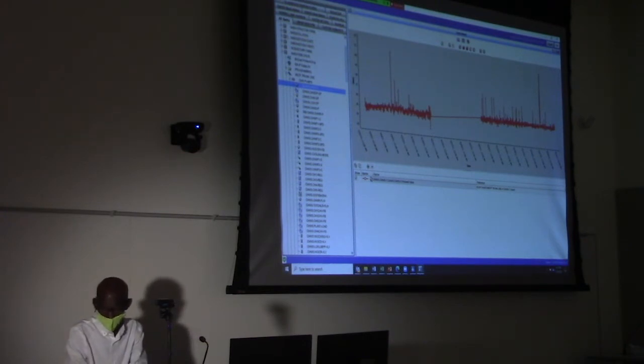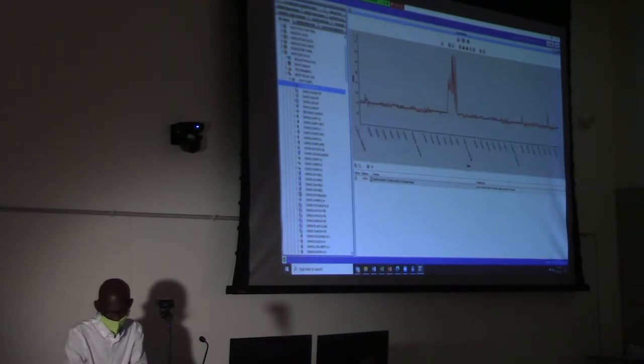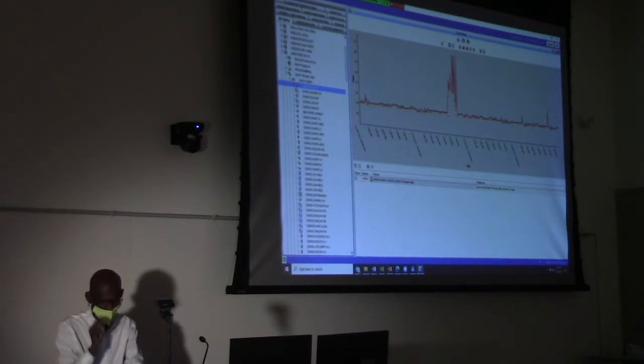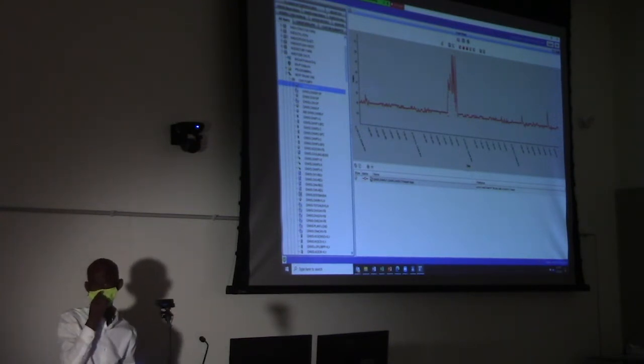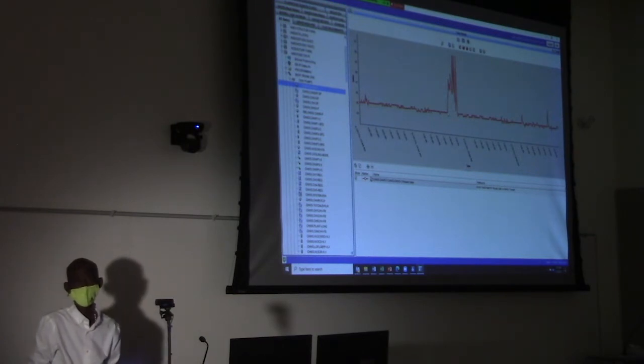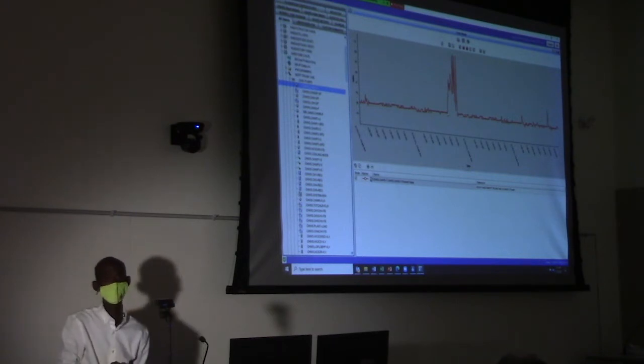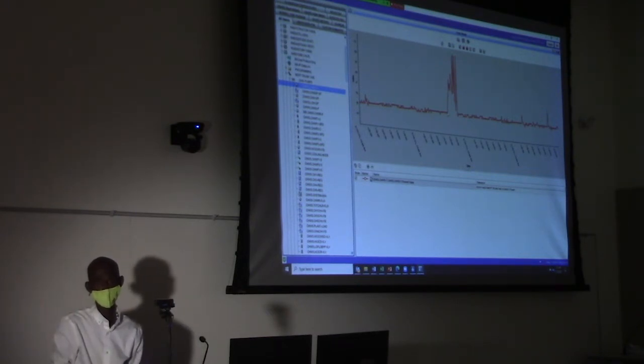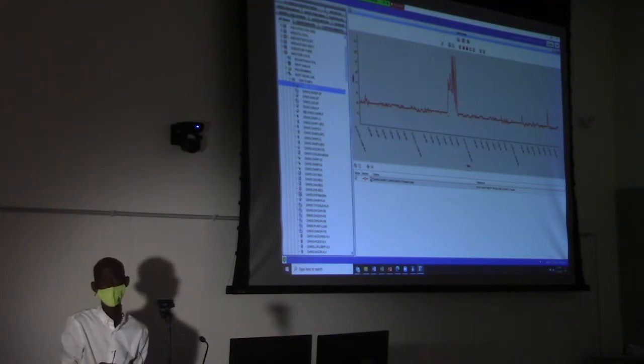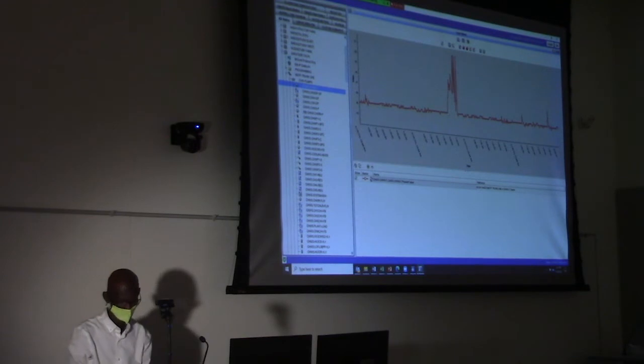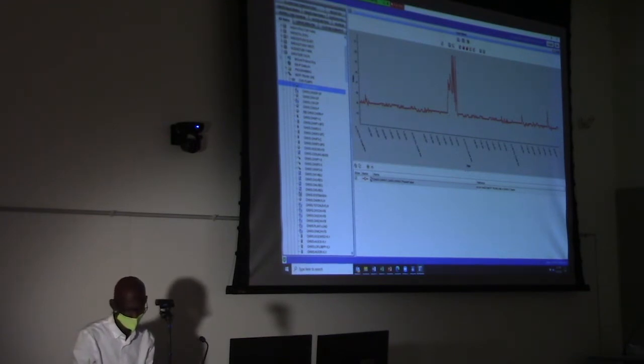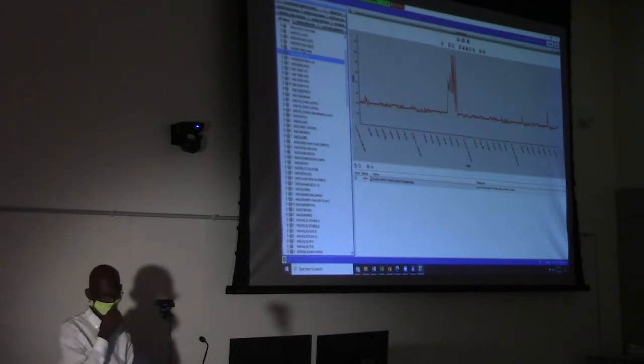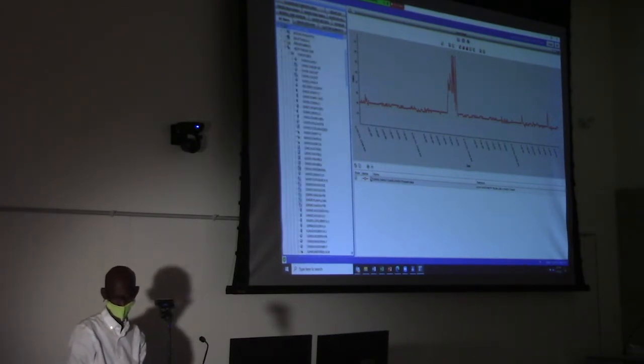But another thing I want to check is probably, was this Labor Day? No. This was a problem. It's not a problem. But if it's 51 degrees, it's not that critical because we're not worried about it until it gets to 55, 56 degrees. When it's 56 degrees, then we have to alert, to get an alarm and do a corrective action. Otherwise, if it's 60 degrees, we may overheat some equipment and damage them.